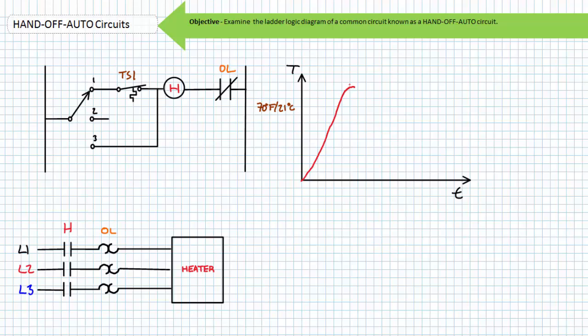As heat in the conditioned space rises to this set point, the temperature switch would open and de-energize the contactor coil and turn off the heater. If heat were to fall below the reset value of the temperature switch, it would return to its deactivated closed state and the heater would come back on.